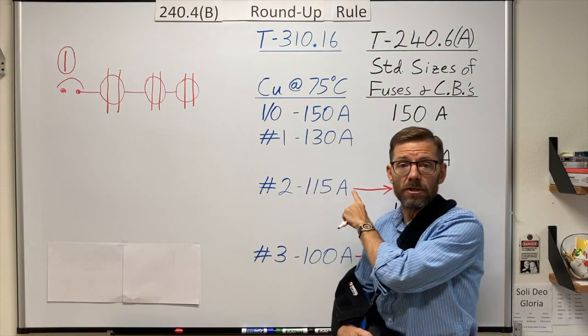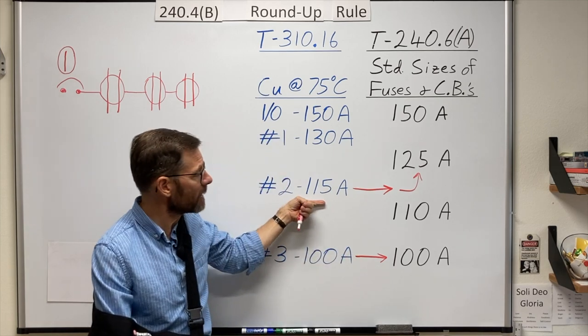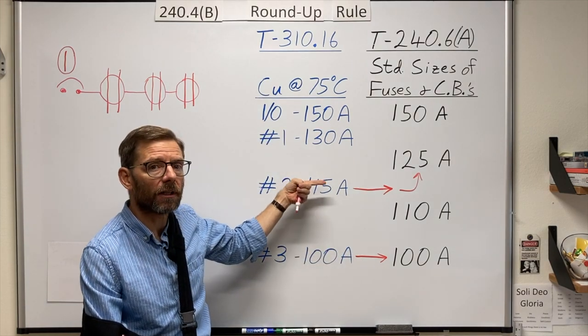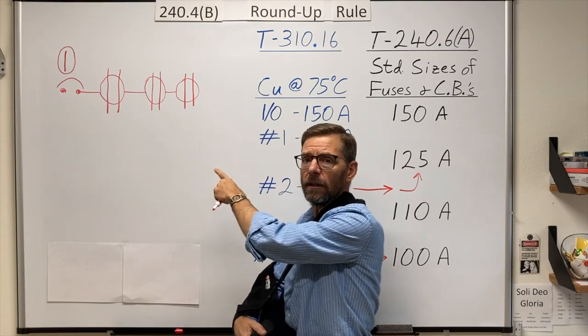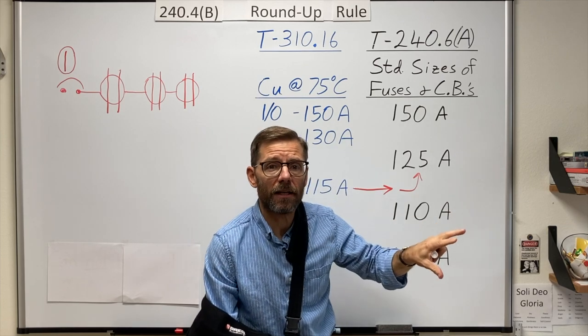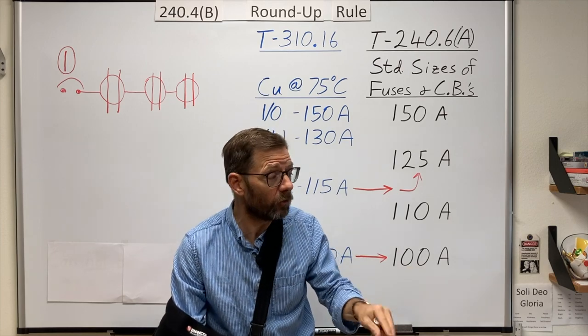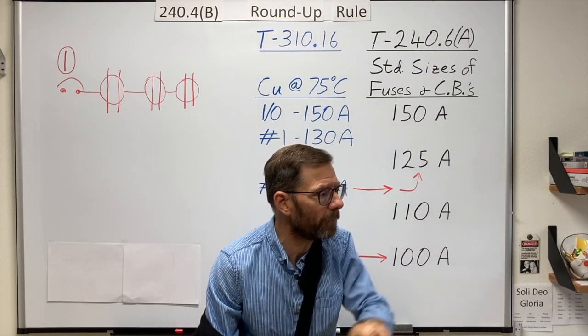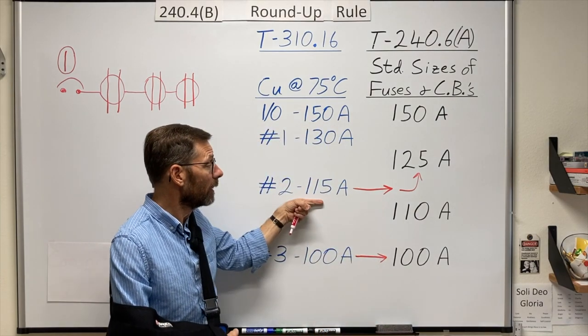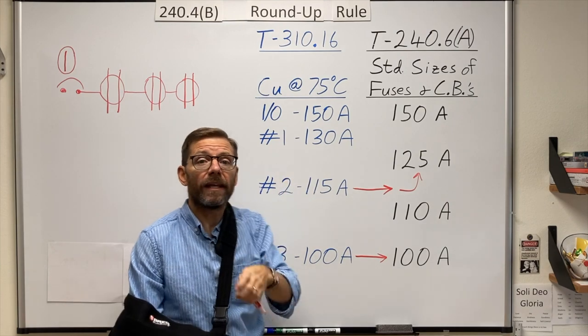I cannot use this provision. And what that does is it gets us to this concept of control. How do we control how many amps are on the conductor? Because if I have a bunch of receptacles that portable equipment is connected into, any member of the public can come along, who doesn't understand our trade and our rules, can come along and start moving equipment, adding extra ones, moving things in and out, and they could unwittingly overload the conductor.